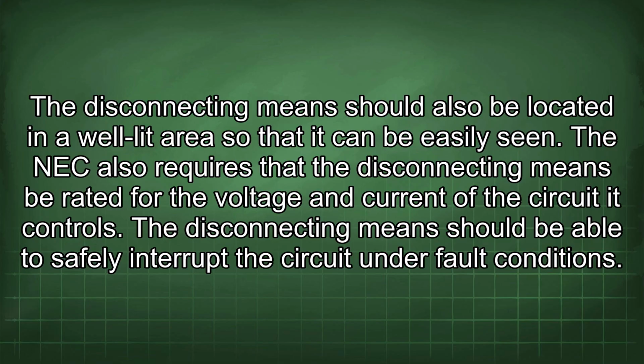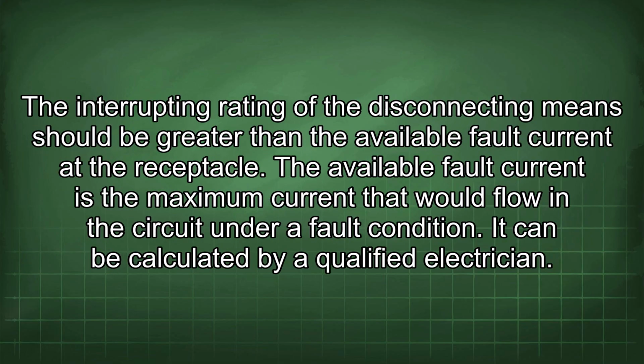The NEC also requires that the disconnecting means be rated for the voltage and current of the circuit it controls. The disconnecting means should be able to safely interrupt the circuit under fault conditions. The interrupting rating of the disconnecting means should be greater than the available fault current at the receptacle. The available fault current is the maximum current that would flow in the circuit under a fault condition. It can be calculated by a qualified electrician.